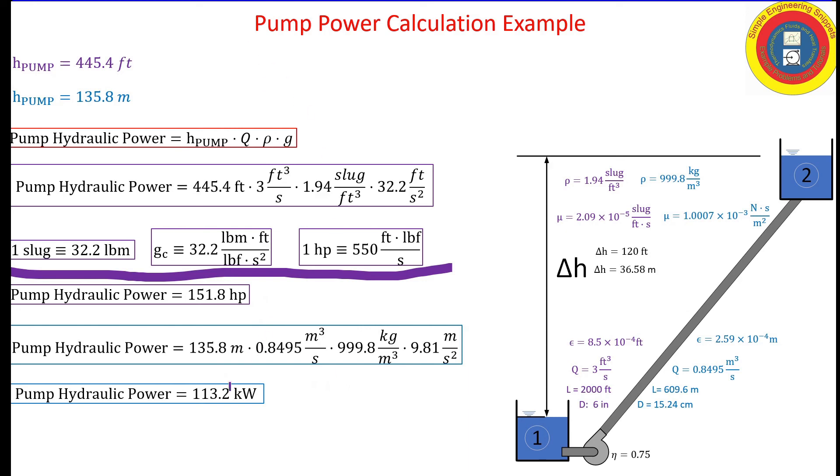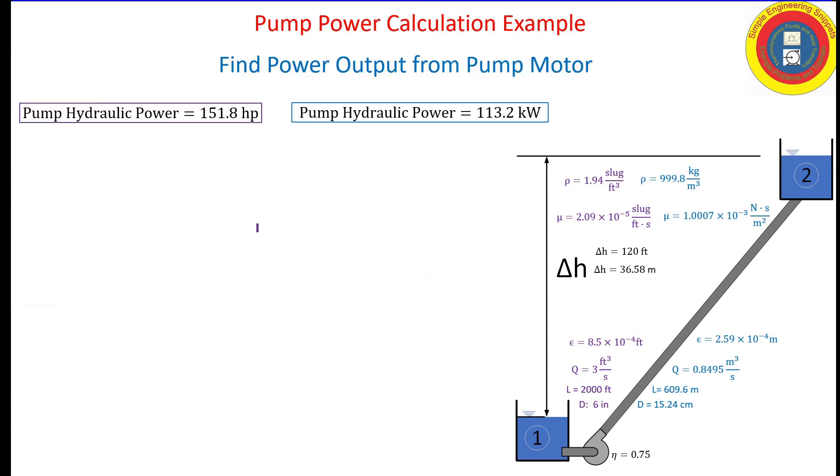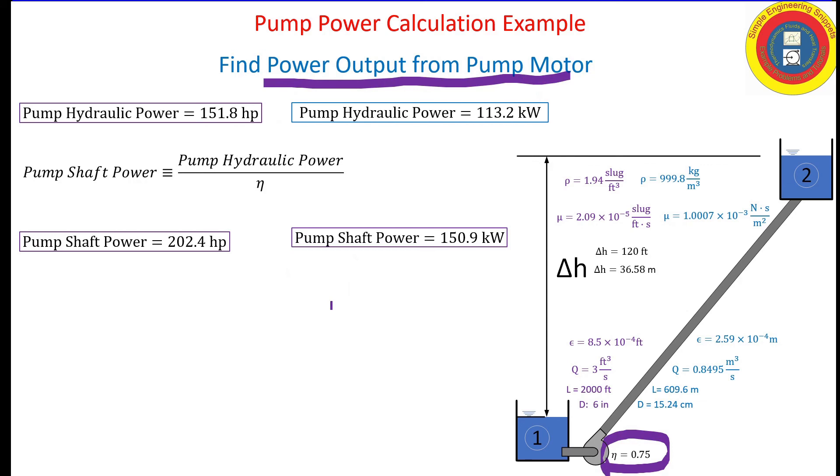That's not really what we were looking for. That is the hydraulic power. That's the power that's necessary for the pump to deliver to the fluid. If the pump is 100% efficient, we would be done. But our pump is 75% efficient. So we need to solve for the shaft horsepower. That's a simple calculation. We obtained in British gravitational units 202.4 horsepower and in SI 150.9 kilowatts.